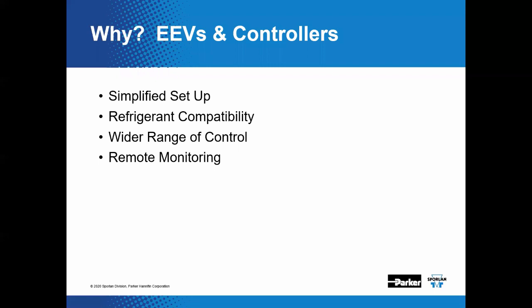The control range is also significantly wider compared to the mechanical version, with less sensitivity to changes in weather and hence load. Glenn, how does that come into play? What does that mean? Well, for example, that first valve we talked about being a 2.5 ton valve, they can actually control all the way down to 10% of the valve's capacity. So roughly 1/4 of a ton. But if you had a standard mechanical thermostatic expansion valve, you could only come down to maybe say 35% of its nominal capacity, meaning it won't control over that wide range.